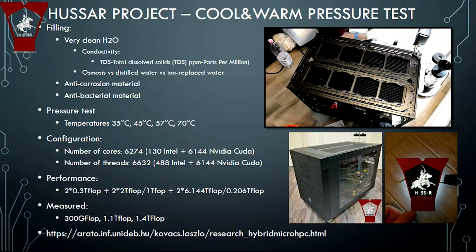And actually, after you put the clear water into the system, after a couple of hours the TDS reaches a little bit higher value. It is because the water pH is very low and can dissolve relatively small amounts of iron and other stuff from the metal components.